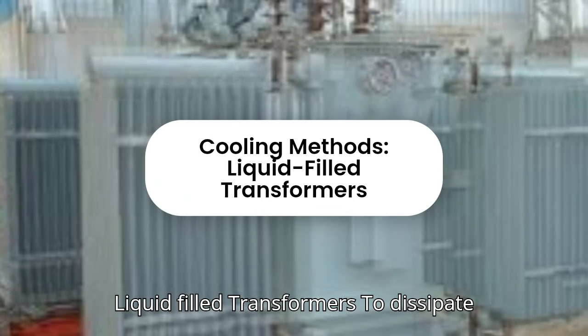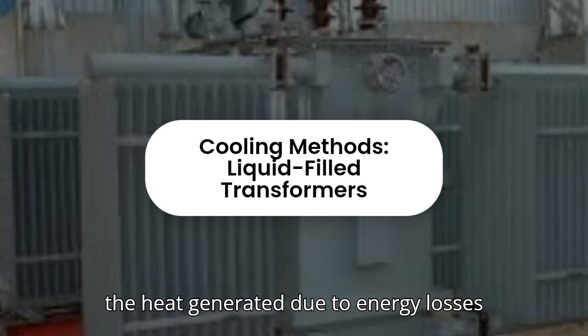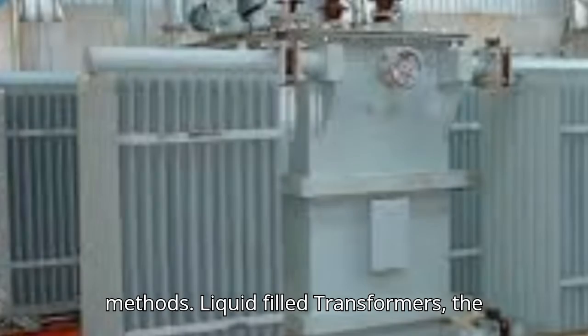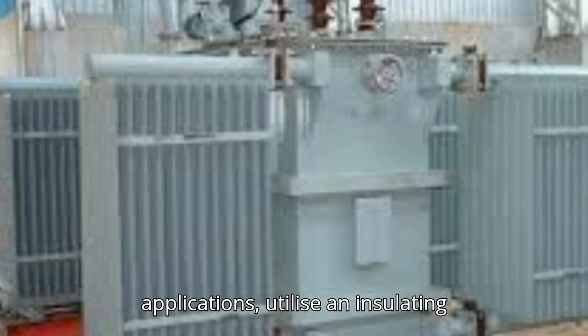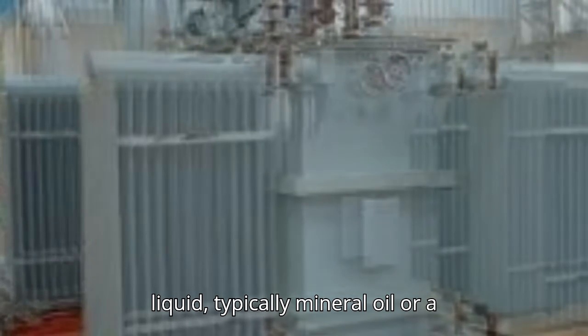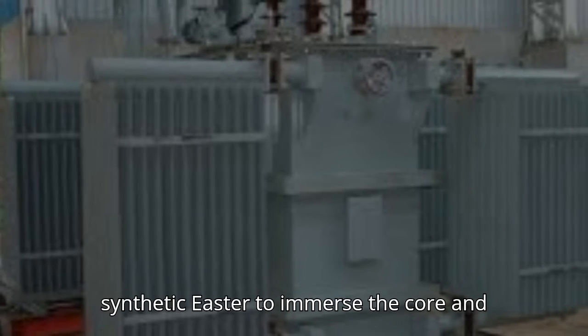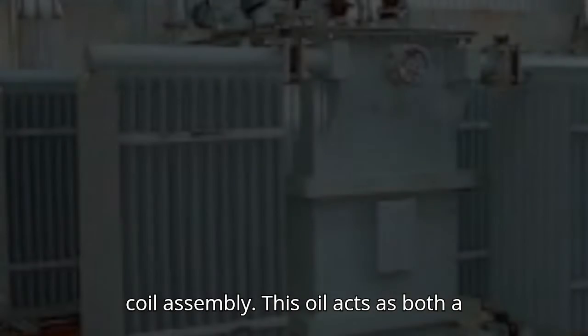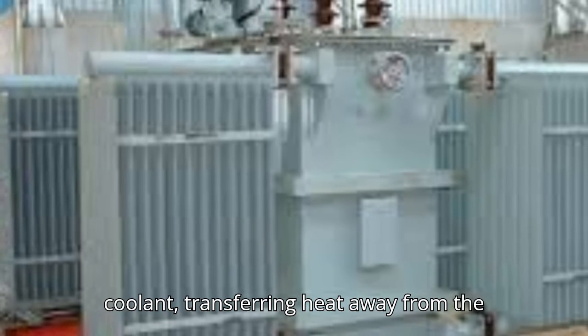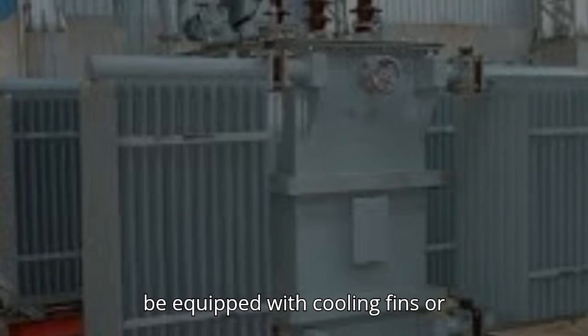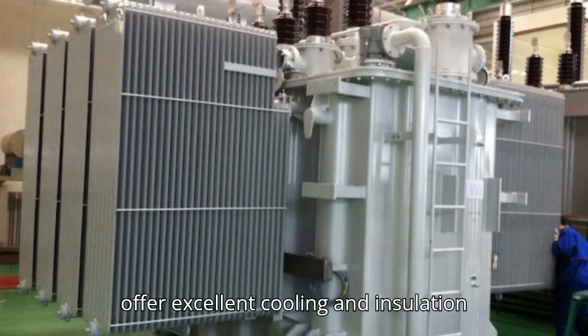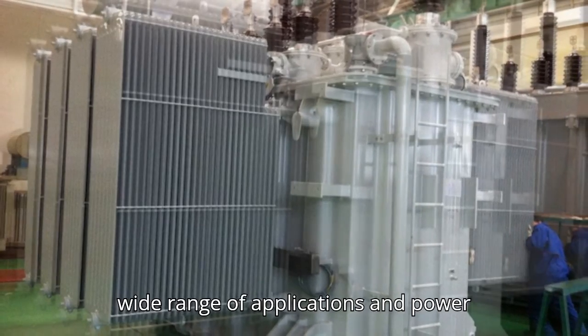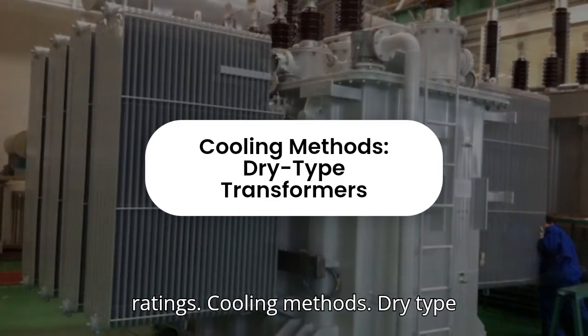Cooling methods. Liquid-filled transformers. To dissipate the heat generated due to energy losses within the core and windings, distribution transformers employ various cooling methods. Liquid-filled transformers, the most common type for outdoor applications, utilize an insulating liquid, typically mineral oil or a synthetic ester, to immerse the core and coil assembly. This oil acts as both a dielectric, insulating medium, and a coolant, transferring heat away from the active parts through convection and conduction to the tank walls, which may be equipped with cooling fins or radiators to further enhance heat dissipation. Liquid-filled transformers offer excellent cooling and insulation properties, making them suitable for a wide range of applications and power ratings.